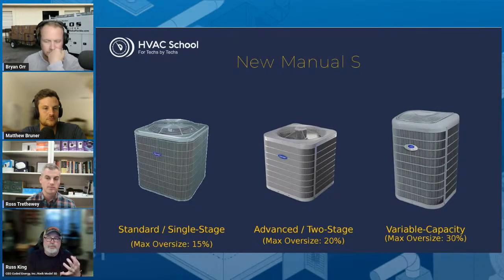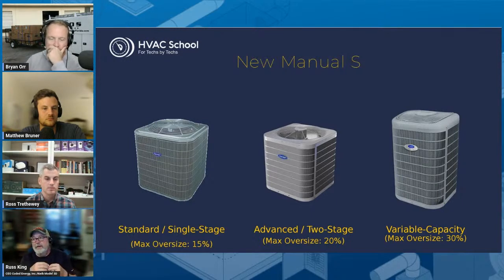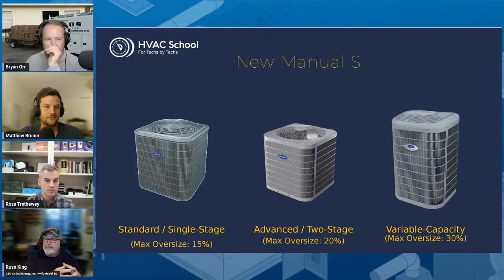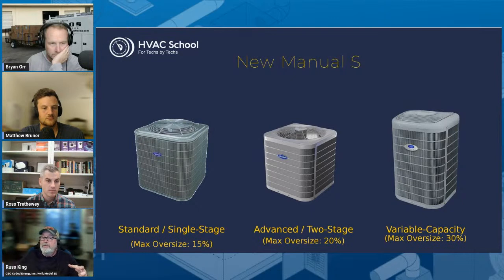And so the two biggest remedies for oversizing the air conditioner are variable speed and good airflow. You have to have good airflow and good mixing and all that other stuff to do it. So yeah, the new Manual S has options for people who want to size without heat strips. If you don't want electric strips, there are options for that. That's the advanced sizing criteria, where you size the heat pump to the heating load, and then you look at the cooling load, and there are remedies for it being oversized. And then of course it depends on the climate too.